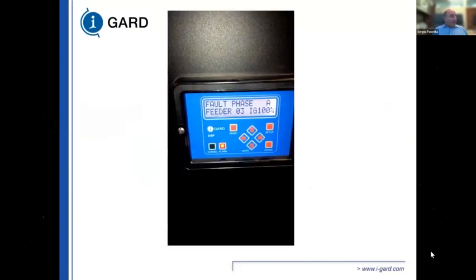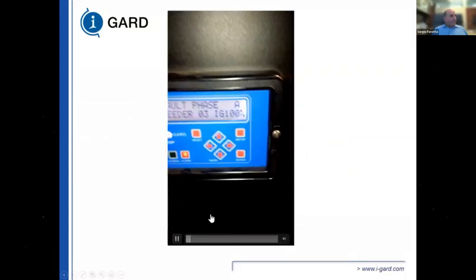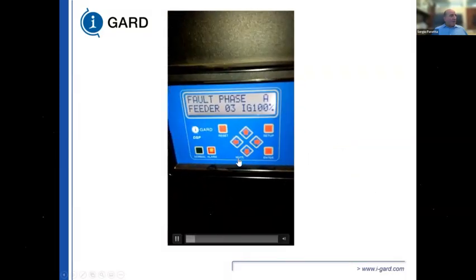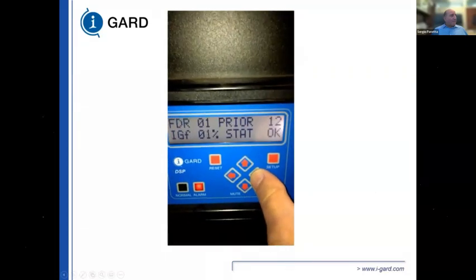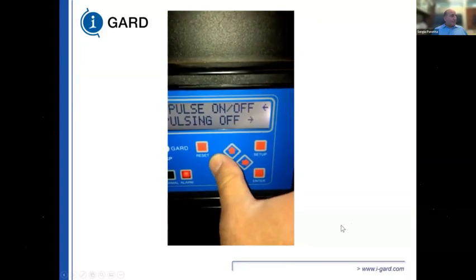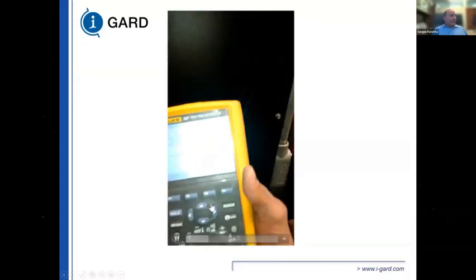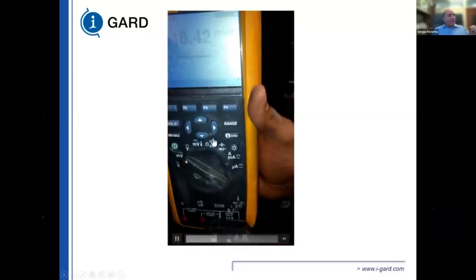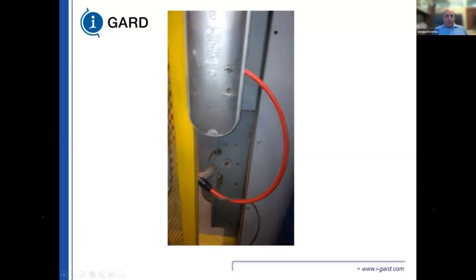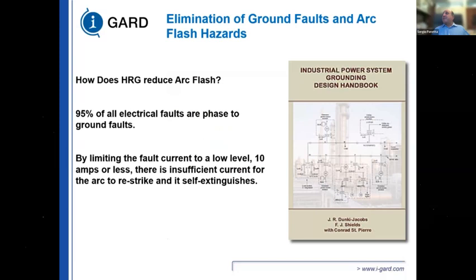So this is the particular relay that we have. We turn on the pulsing. It's hard to tell, but if you look at that bar graph over there, you can see it changing, high, low, high, low. We're looking at the path of the fault. And I've got this around the conduit, the elbow, it's grounded. Now you've heard the expression that current takes the path of least resistance. Not true. Current takes every single path that's available to it. So you can find where the fault is without opening up any doors and exposing yourself to a greater hazard.